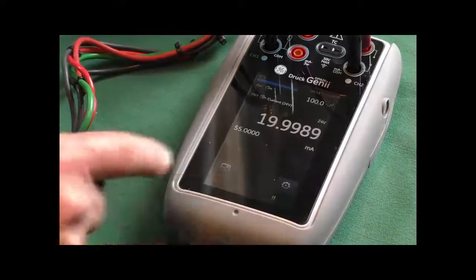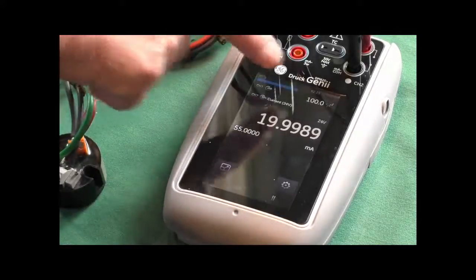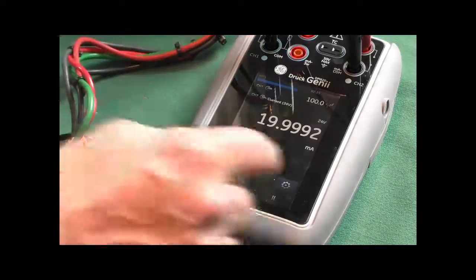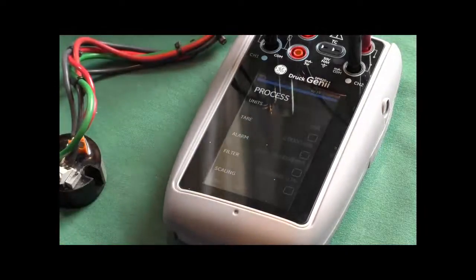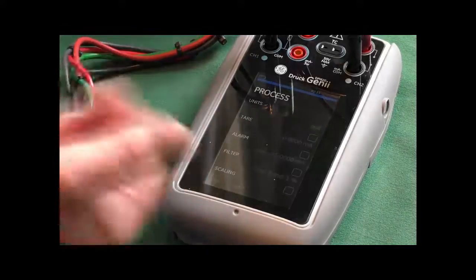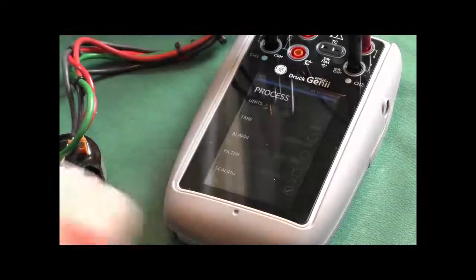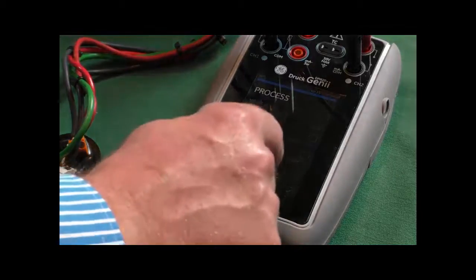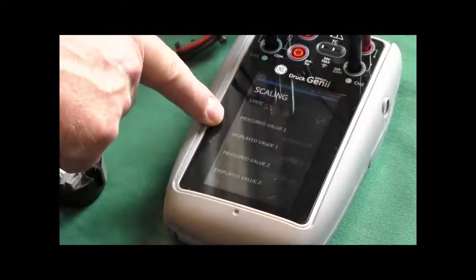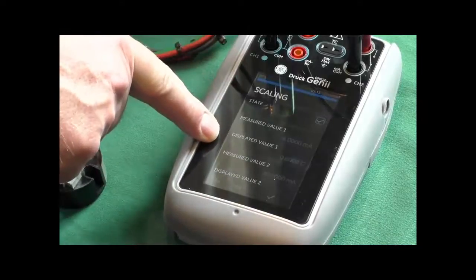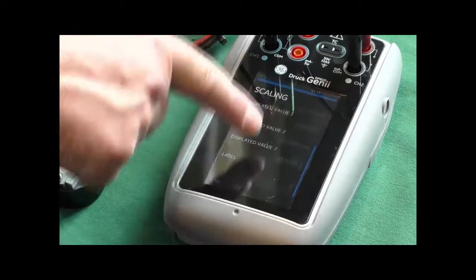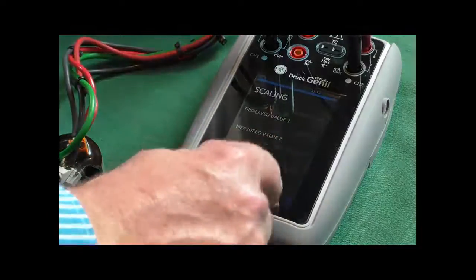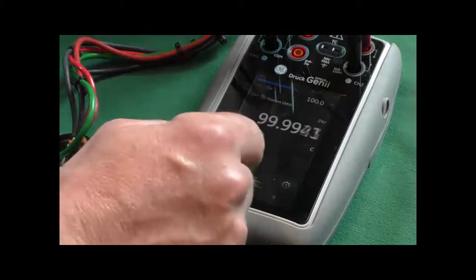One of the nice features we can do on the configuration, obviously at the moment we are sourcing and simulating temperature and reading milliamps out. What we can do is turn the scaling on in the system here. So instead of looking at 4 and 20 milliamps and working out what that is in degrees C and the error, we can turn on the scaling quite simply. And in the scaling, I'll just scroll it up a little bit. So on the scaling, we can enter the measured value here is 4 milliamps equals 0 degrees C, and the measured value at 20 milliamps equals 100 degrees C. I can change that label to F or whatever or percentage, anything I need. Hit the tick button and come back.